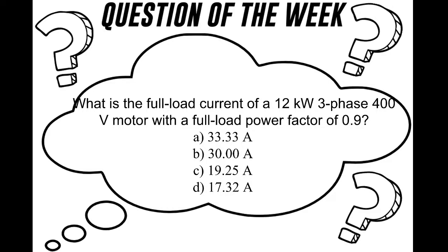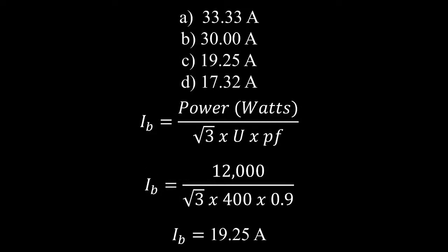So to put people out of their misery, the formula we were going to use would have been the power of the motor divided by √3 times the line voltage, and then multiplied by the power factor. In our instance it was a 12 kilowatt motor, which means 12,000 watts. We knew that our line voltage was 400 volts and the power factor was 0.9, so it was a case of crunching those numbers through that calculation to give us a value of 19.25 amps. But normally you would also factor in the motor efficiency. Totally agree with the people that made those comments on social media.